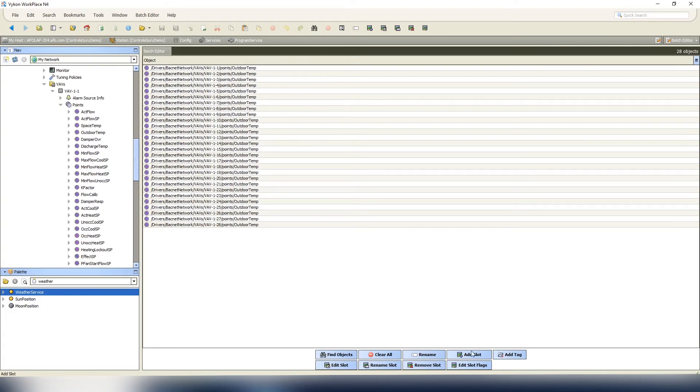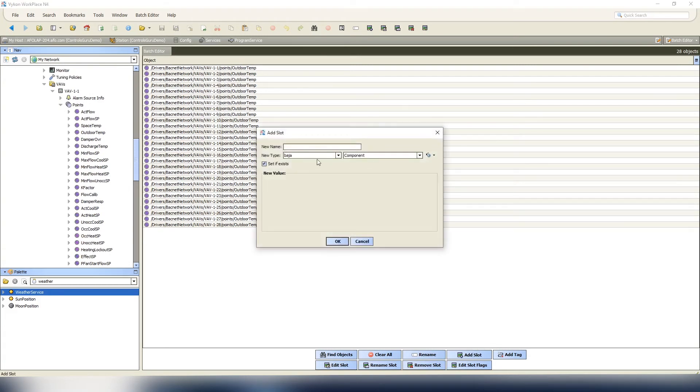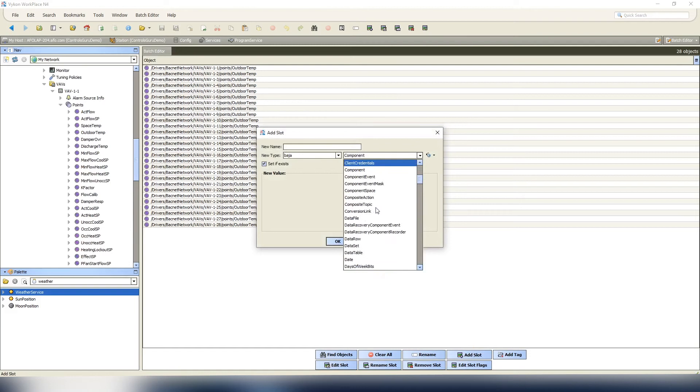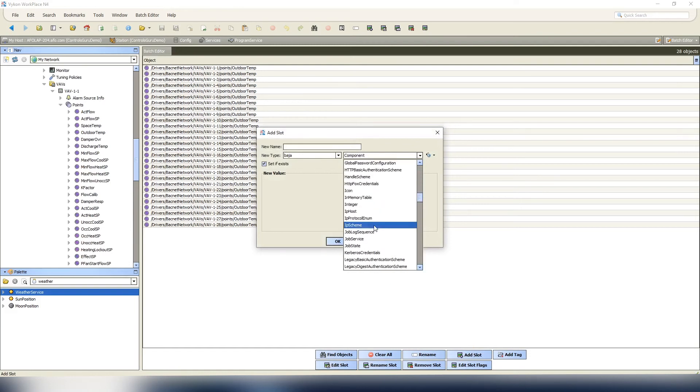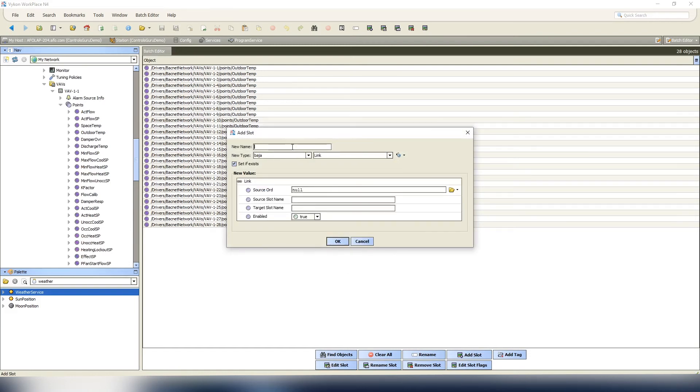What we're gonna do is we're gonna go ahead and add a slot through the Baja. We're gonna look for a point called link. Name it whatever you want to name it - something that makes sense to you. So we'll say global OAT link in 10. That just makes sense to me - the global outdoor air temp we're linking to input 10.